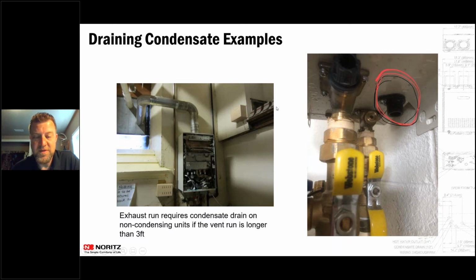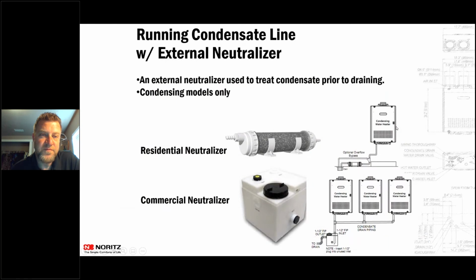Everything you guys would install in the future is going to be condensing anyway, so that's not a great example. But over here on the right, you can see what that drain would kind of look like. You can see that on this install, they didn't install that, so that condensate was just dripping straight on the floor. Condensate will eat concrete after a while, so you want to make sure that you are taking that all the way down to that drain on the outside.